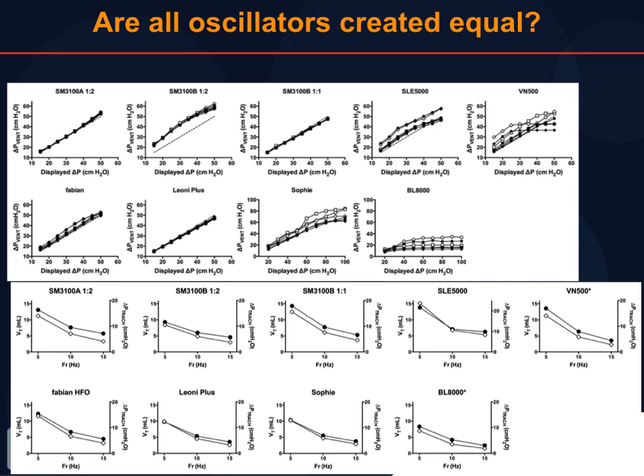and then there's a UK device, the SLE, and the SLE at the time of testing only had a 1-to-1 IE ratio. So consequently, when we tested it, we also had to run one of the other devices at a 1-to-1, because that in itself is a major influence on delta P and performance, is the IE ratio. We decided to test all of them essentially at 1-to-2, because that's what in Australia at least we will use as a default. But we've got a 1-to-1 here for comparison for the two Sensormedics.